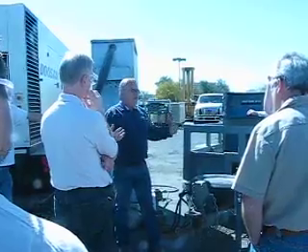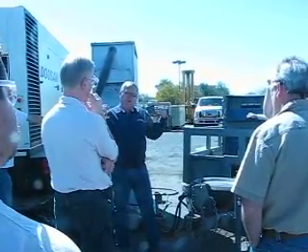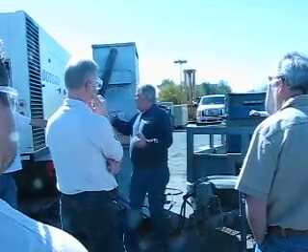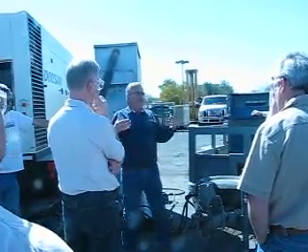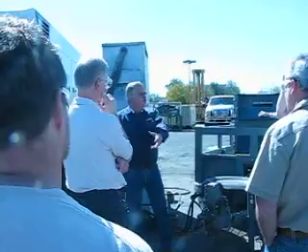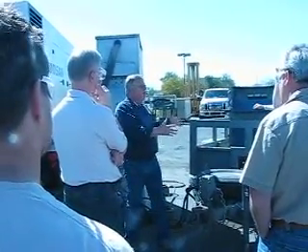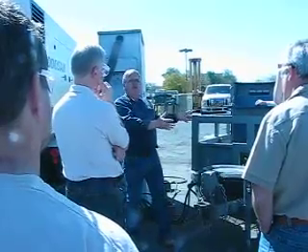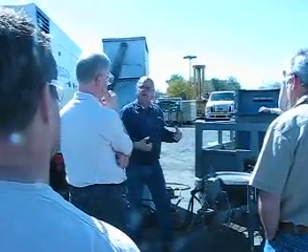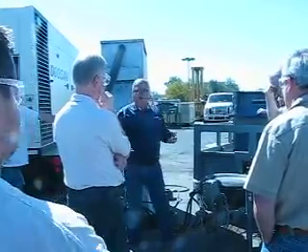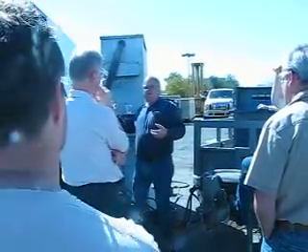So whenever you're paralleling generators, you should go through a commissioning process. That commissioning process should include kVARs so that you're not only testing the prime mover and KW and load sharing, you're also testing how the generator voltage regulators are sharing the kVARs of what's going to be the load. So instead of using the building, you're bringing your own in.